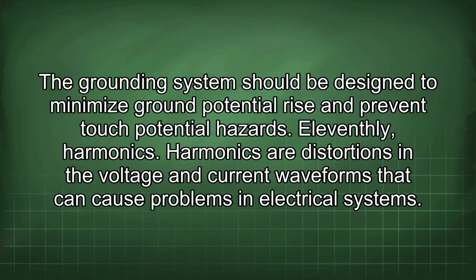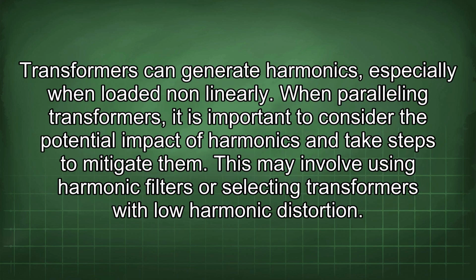Eleventhly, harmonics. Harmonics are distortions in the voltage and current waveforms that can cause problems in electrical systems. Transformers can generate harmonics, especially when loaded nonlinearly. When paralleling transformers, it is important to consider the potential impact of harmonics and take steps to mitigate them. This may involve using harmonic filters or selecting transformers with lower harmonic distortion.